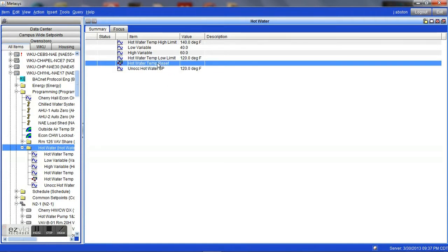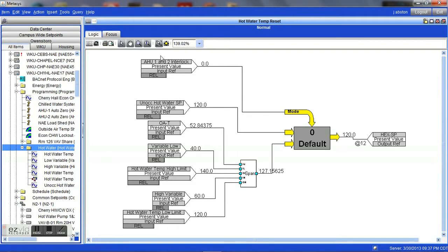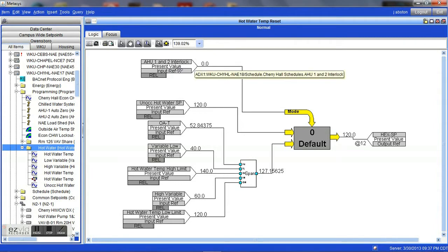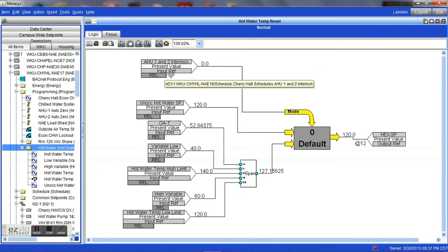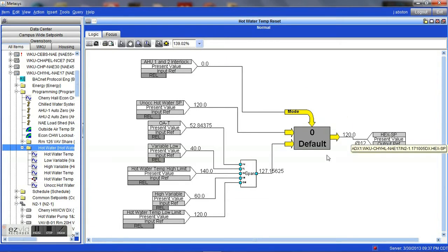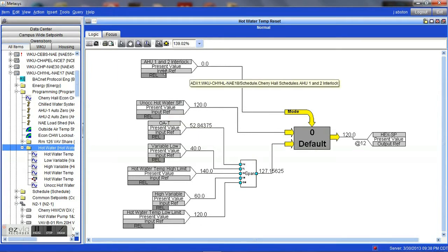Through the logic we will ramp that system back up whenever the demand is needed. In this control loop, a few other points that we have pulled in relate to whether or not our air handler is running. We have an input reference here that looks at the air handlers. If we're calling for our air handlers to be on — which you see here is zero, meaning that it is not — we go through this switch. Based upon the condition of our air handler, this switch will either adjust the hot water supply temp to a calculated value or to the unoccupied hot water set point.